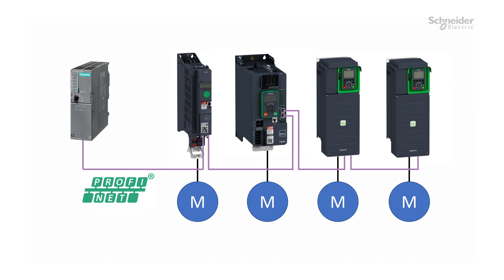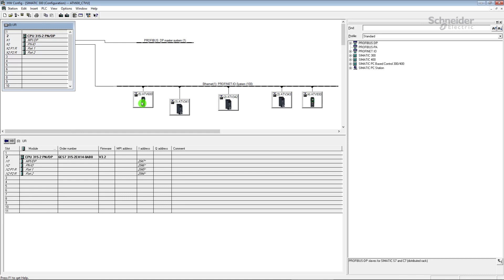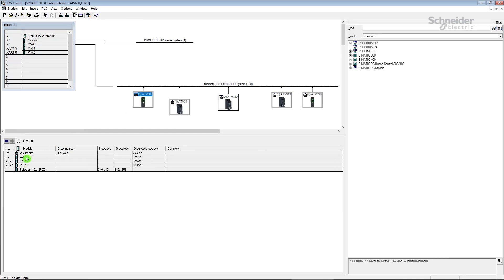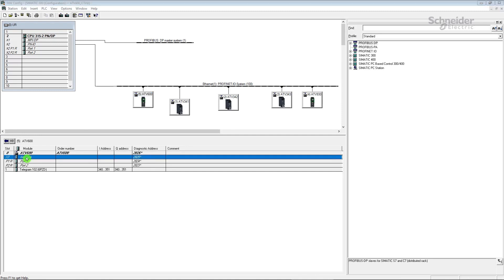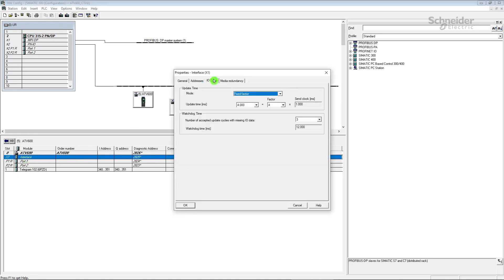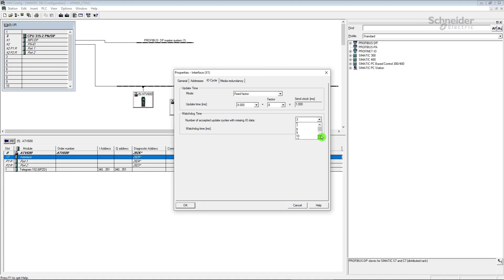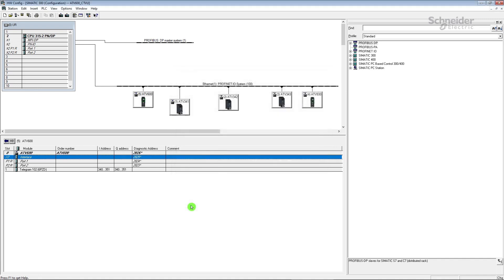Now let's see the example with PROFINET. Open the hardware configuration of your application and select your drive, then go to the interface. To change the timeout — called the Watchdog Time — you must increase the Update Time and the number of accepted cycles with missing IO data. The Watchdog Time is updated automatically. Click OK, save the configuration, and click on Download to Module.